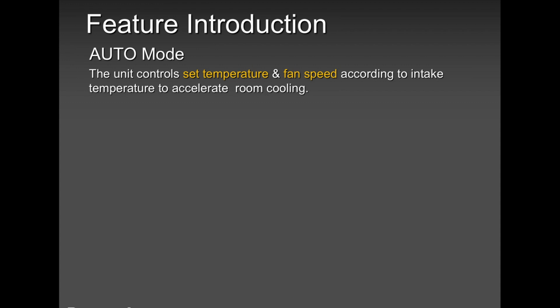But where office application is concerned, auto mode is not a bad feature, because in the morning nobody's there, it's cold outside, it runs in heating, and then as time progresses, it gets very hot, it goes into cooling. So that's fine in office spaces, but at home I prefer to leave it in either cooling or heating. At this time of the year, where we have spring summer conditions, I prefer using my window, fresh air. So it all depends. Okay guys, the mode is there, the feature is there, it's up to you and it's up to the homeowner. But this is my experience and this is my perspective.